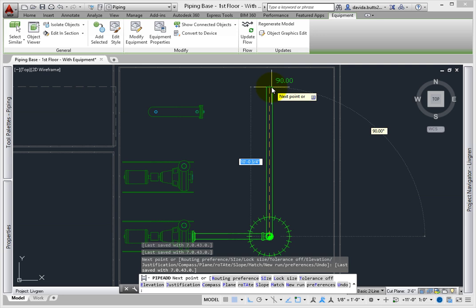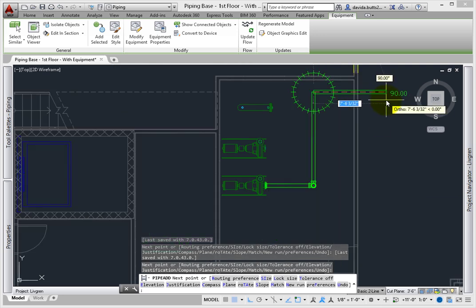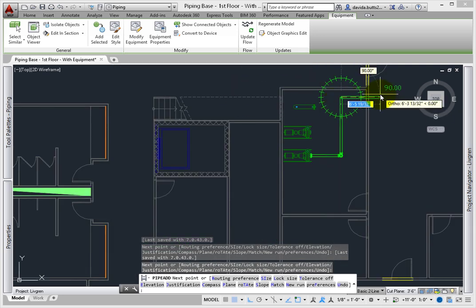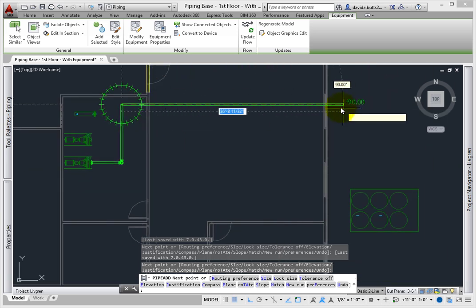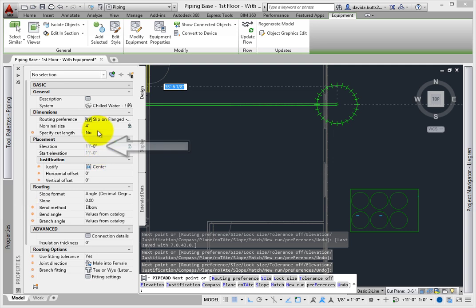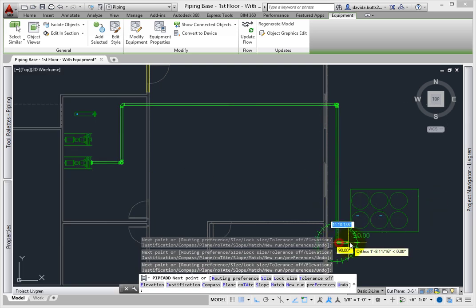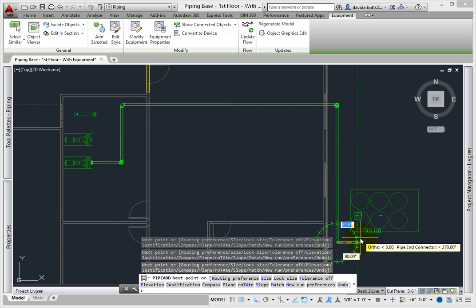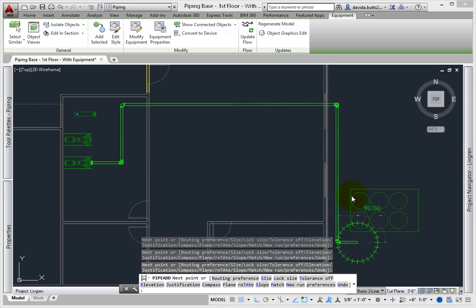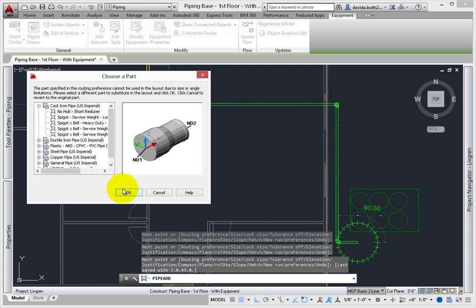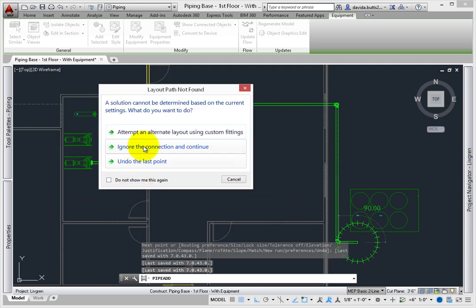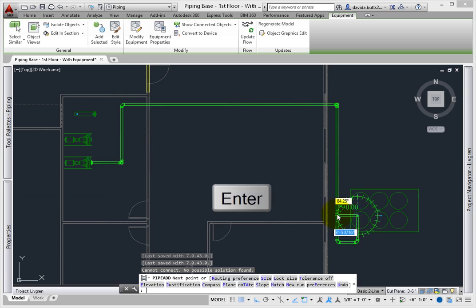Draw a short segment up past the heat exchanger, and then turn right to go out of the building. Once outside the building, drop back down to a 6-inch elevation. If O-Track is turned on, watch as a tracking line appears — this helps you line up connections between the pipe and the fitting. Pick a point when this appears. Next, use the snap to create a connection to the chiller. The routing solutions will appear to help you create a layout that works with the fittings. Cycle through these by picking the next option, but use the first solution — this connects the pipe to the equipment correctly. Press Enter to complete the piping command.